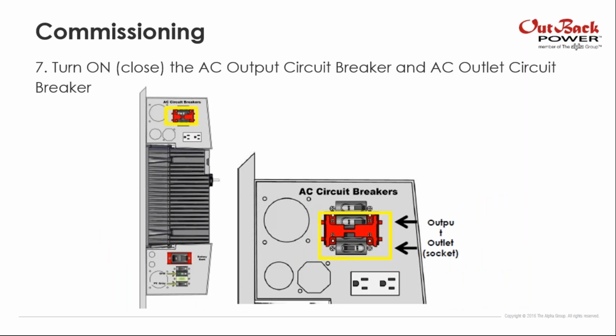Then you have to turn on the AC output circuit breaker and the AC outlet circuit breaker. In every FLEXpower one, you have an AC outlet right here and it has its own circuit breaker. So when you turn it on, you could check the voltage and polarity in the outlet.